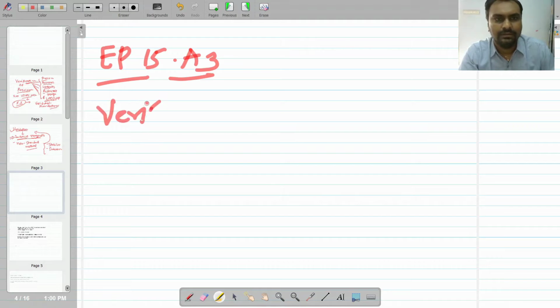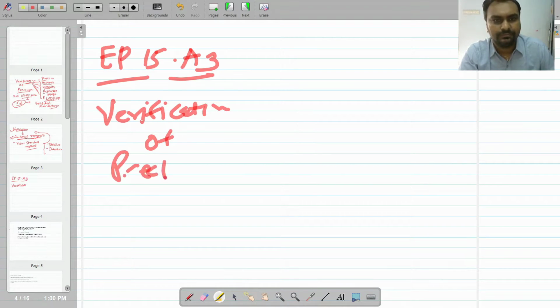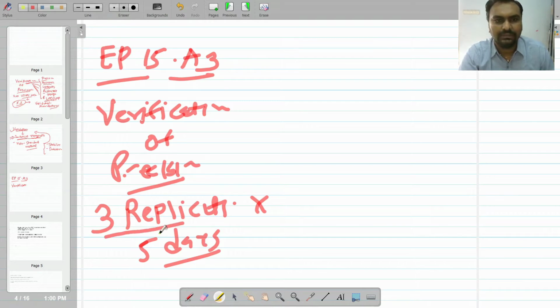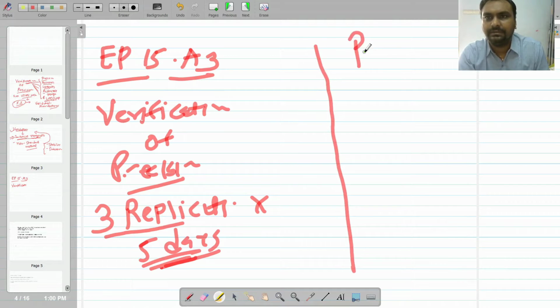EP15-A3 verification of precision: 3 replicates of one sample for 5 days are required, and we calculate the SD and CV of all the results that we got and check whether our SD and CV are less than the manufacturer's claim or not.